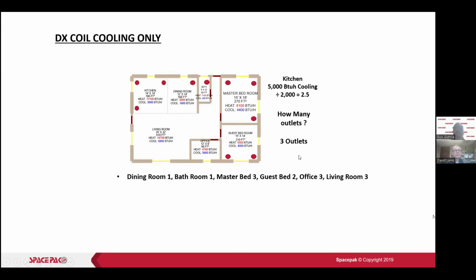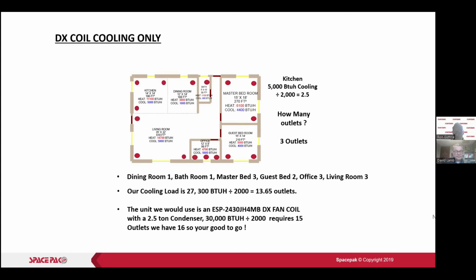So this exercise goes through that, and it says how many outlets you want to put in the room is based on the larger number of outlets required, from either the cooling or the heating BTU load. Then we look at our total outlets and say, well, we've got a 2-ton or 2.5-ton system, and we've got 13.65 outlets.